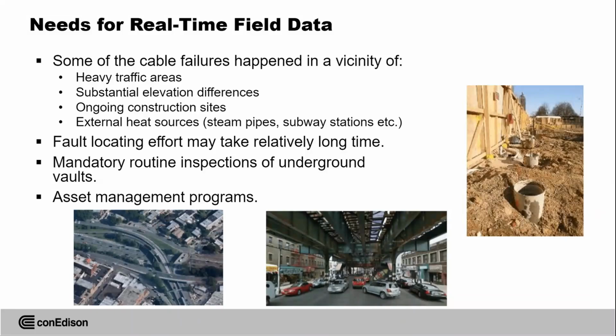Before we analyze what happened in our system in, let's say, the last 20, 30 years, we see some of the cable failures happened in the vicinity of heavy traffic areas, substantial elevation differences, ongoing construction sites, or near external heat sources, steam pipes, subway, other transmission circuits, or distribution circuits. Fault locating effort may take a relatively long time because in the urban environment, we install our system in a duct bank, in ducts, basically underground. So we're not allowed to dig everywhere to get access to the cable. We only have access to the vaults. And that's why fault locating may sometimes take a long time.